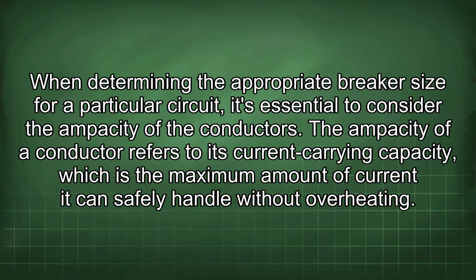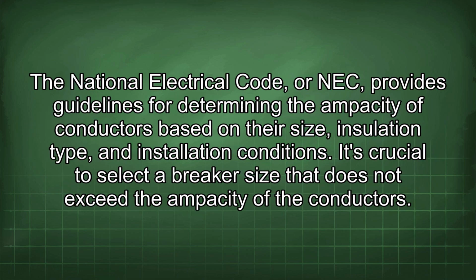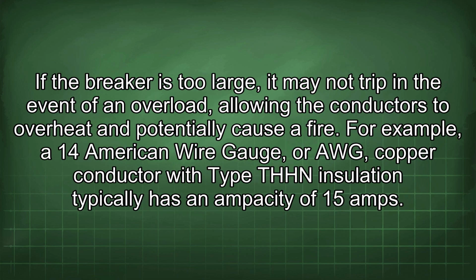When determining the appropriate breaker size for a particular circuit, it's essential to consider the ampacity of the conductors. The ampacity of a conductor refers to its current carrying capacity, which is the maximum amount of current it can safely handle without overheating. The National Electrical Code, or NEC, provides guidelines for determining the ampacity of conductors based on their size, insulation type, and installation conditions. It's crucial to select a breaker size that does not exceed the ampacity of the conductors. If the breaker is too large, it may not trip in the event of an overload, allowing the conductors to overheat and potentially cause a fire.